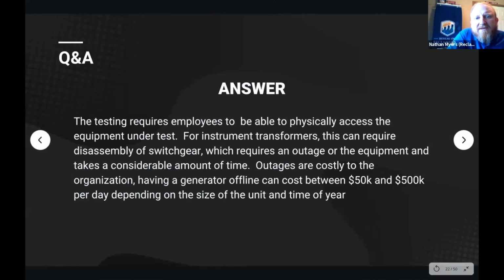So the testing requires employees to be able to physically access the equipment under test. And for instrument transformers, as I mentioned, it can require disassembly of switchgear, which requires an outage of the equipment and takes a considerable amount of time. Outages are costly to the organization. For example, having a generator offline can cost anywhere from $50,000 to $500,000 per day, depending on the size of the generator and the time of year.